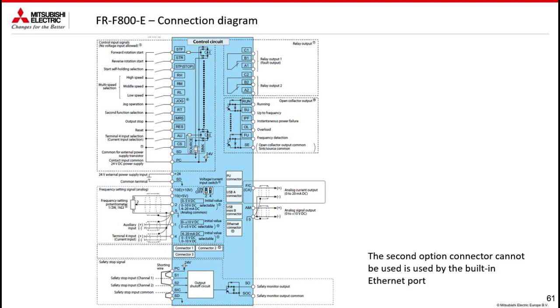In this inverter, there is a double dip switch, one for each analog input, so that both analog inputs can read current and voltage. For safety, by default from PC, the 24 volt is brought to S1 and S2. However, the safety common is released, so we have as common no longer SD but SIC, which stands for safety input common, and which must be closed on SD. At the output, there is a second relay that works like the one previously explained, but by default it does nothing. So if you want to use it, you will need to parameterize it.